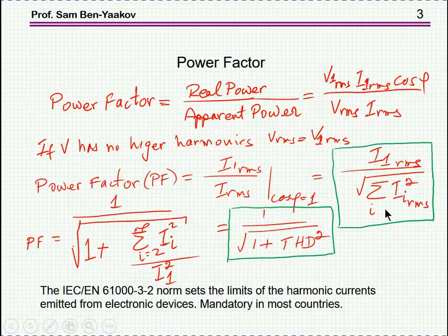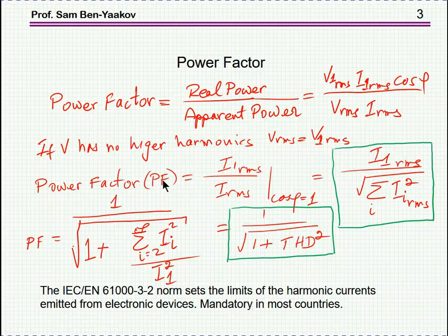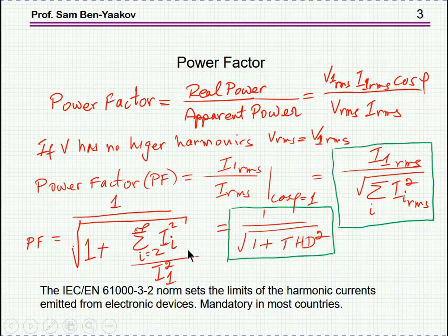On the other hand, if there's no distortion, then the sum will be only the first component, and therefore the ratio will be one. So a power factor of one means there's no distortion of the current, while THD will be zero. As distortion develops, power factor will be smaller and smaller, and THD will be higher and higher, according to these relationships.